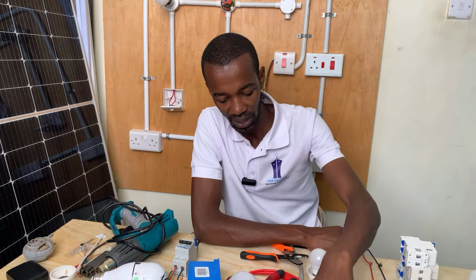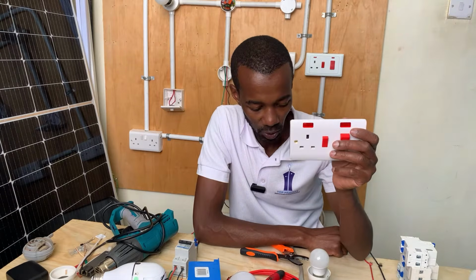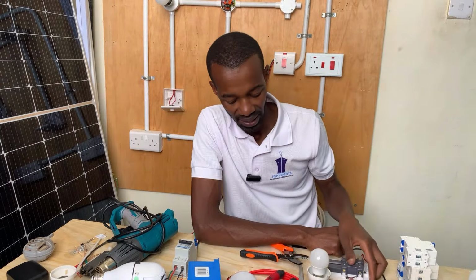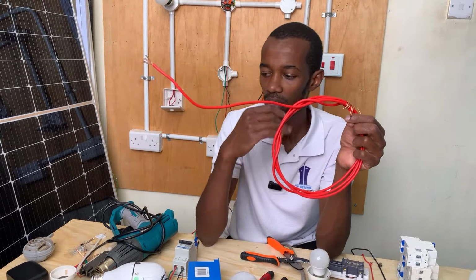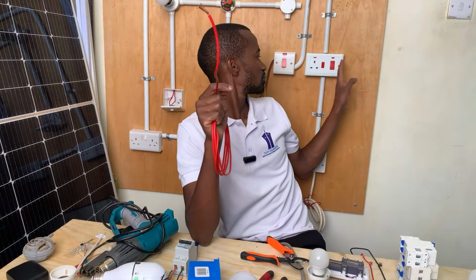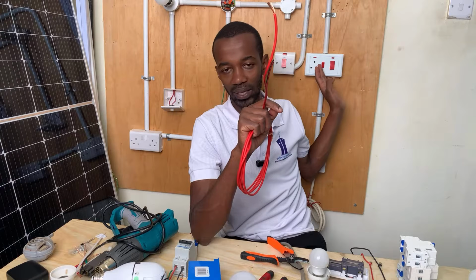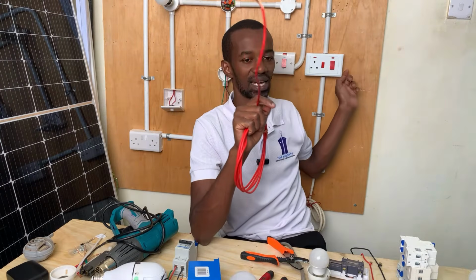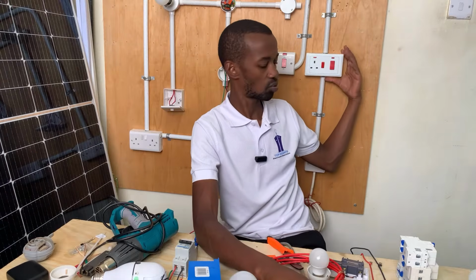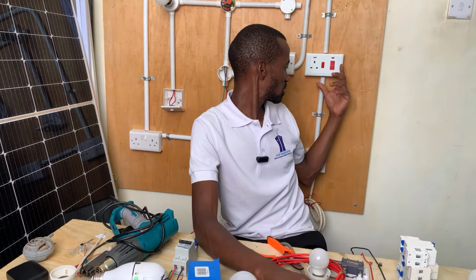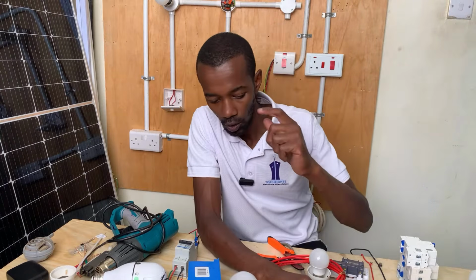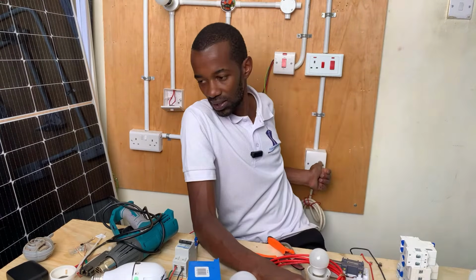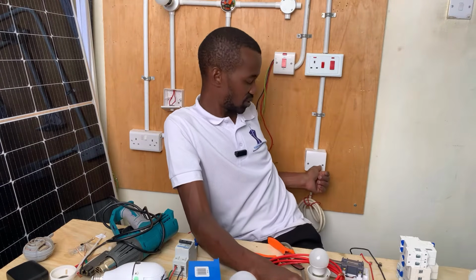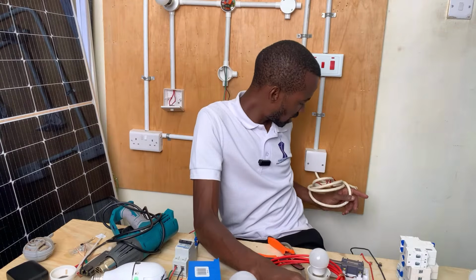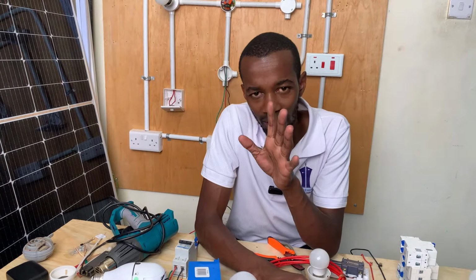Another important aspect for these key circuits, like the cooker, is that the cable size used should be 6.0 all the way from the consumer unit. This is a demo of what we normally have in the house. From the consumer unit, that circuit goes to the cooker unit, then down to the cooker connector. Here is our cooker connector, and from here we feed the cable to the cooker. That cable is a 6.0.